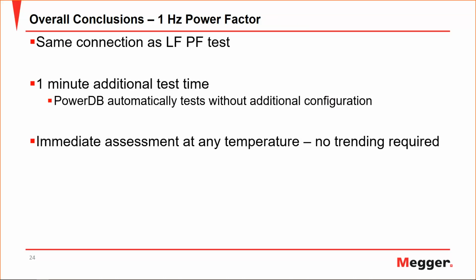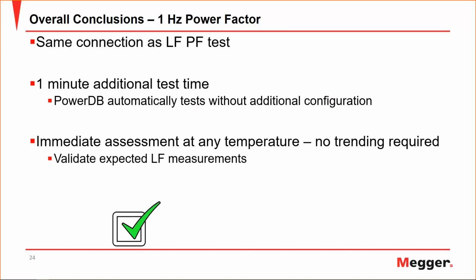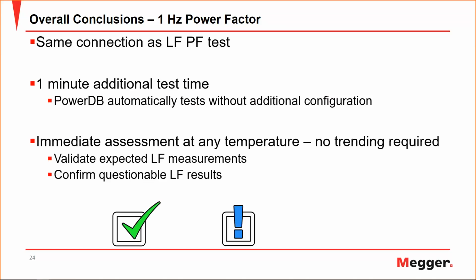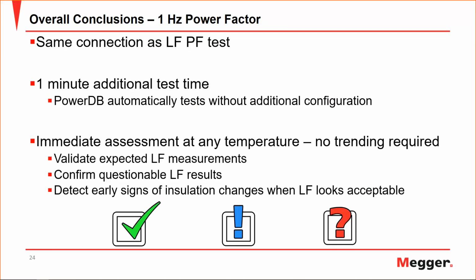When we do this at 1 hertz, we are able to give you an immediate assessment at any temperature without any trending required. We can use this information to validate expected line frequency measurements, confirm questionable line frequency results, and most importantly, detect early signs of insulation changes when line frequency looks acceptable. So when you have one of these test sets that will test 1 hertz at 250 volts, you can implement this 3-step insulation evaluation method.